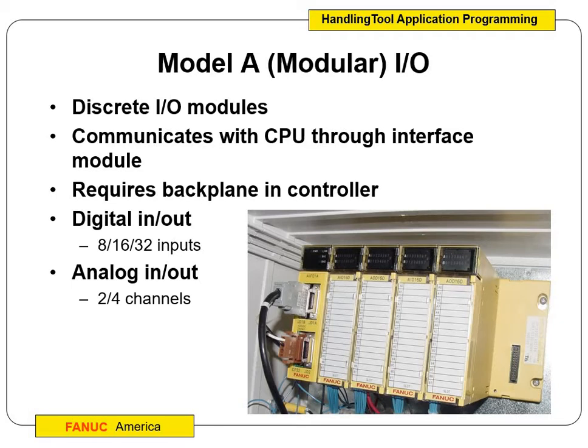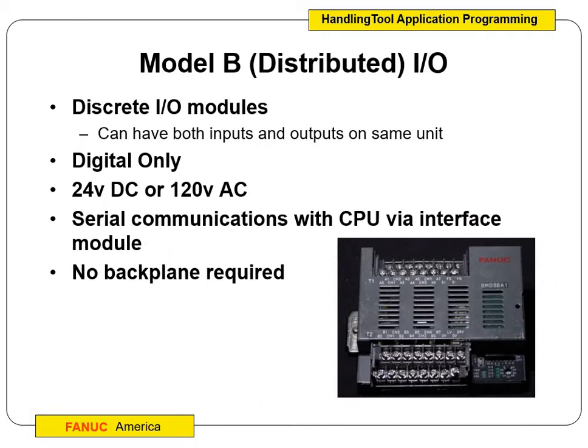This is very similar to the PLC class. We have modular I/O — modular inputs and outputs. Modular means that we can add to them; we can keep adding modules to grow. They are discrete I/O modules and they communicate with the CPU through the interface module, and it does require a backplane in the controller so we can attach and connect everything. Digital inputs and outputs can come in 8, 16, or 32, and we can also have analog inputs and outputs. If we look at model B controllers — digital only, 24 volt DC or 120 volt AC, no backplane required — but ours all look like the modular type.